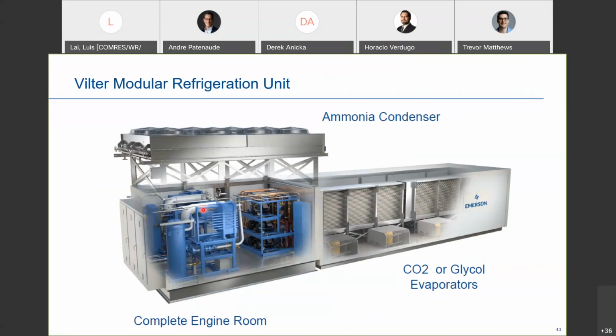So you've got ammonia on the primary, simple cascade chilling CO2, and the CO2 is your low temp CO2 section, and the CO2 is pumped in these evaporators which are attached to the unit, and the air is just blown down into that cooler area, that warehouse area. So it's kind of like a window shaker for industrial refrigeration, if you will. You cut a hole in the roof, and all your refrigeration is contained within the MRU with the gas cooler and/or condenser or evaporative condenser sitting on top. So there's variations of this model, but it kind of gives you an idea what the team's been working on and have just recently launched.